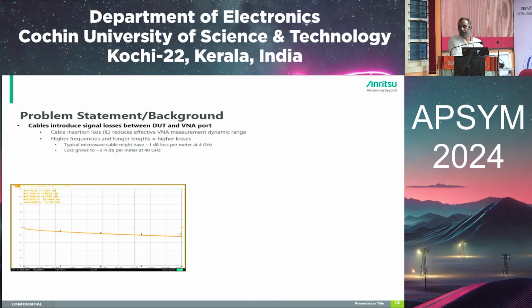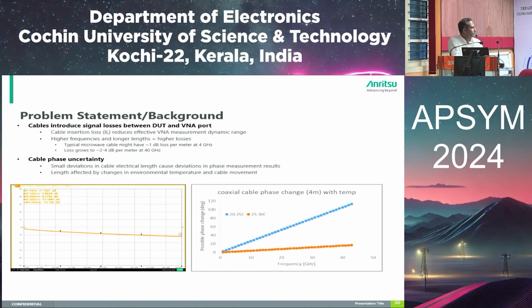And when you go for longer cables, there is an issue of the phase also. Whenever you are measuring the magnitude and the phase, if you move the cable, automatically the phase also varies. So this is the issue we are getting in some of the measurements with long cables. The length of the cable affects the phase and the loss of the cable. As you can see here, if the coaxial cable is 4 meters, with temperature the phase can vary around 120 degrees at 40 gigahertz.